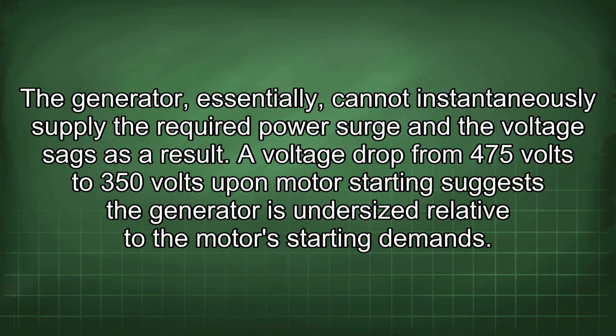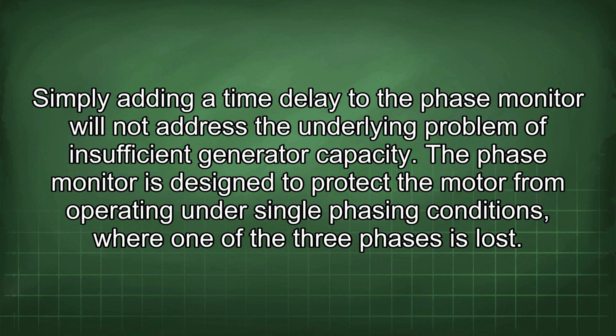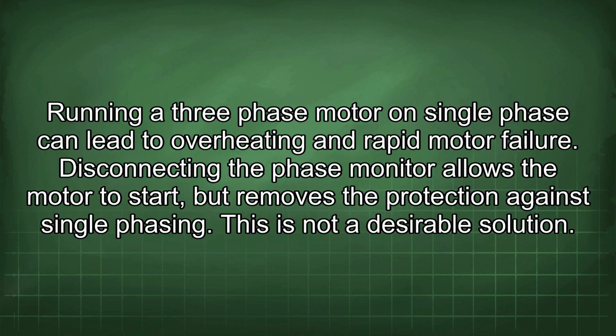A voltage drop from 475 volts to 350 volts upon motor starting suggests the generator is undersized relative to the motor's starting demand. Simply adding a time delay to the phase monitor will not address the underlying problem of insufficient generator capacity. The phase monitor is designed to protect the motor from operating under single-phasing conditions, where one of the three phases is lost. Running a three-phase motor on single phase can lead to overheating and rapid motor failure. Disconnecting the phase monitor allows the motor to start, but removes the protection against single phasing. This is not a desirable solution.